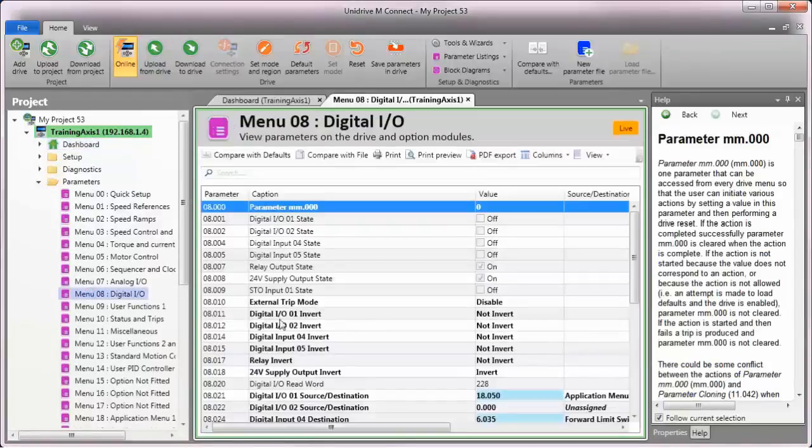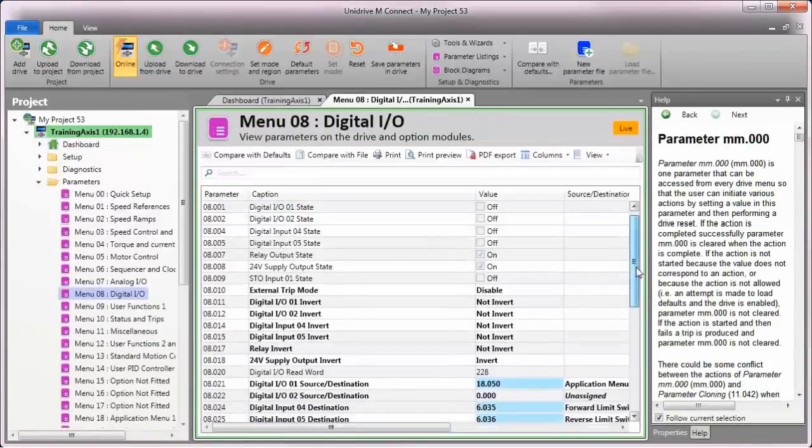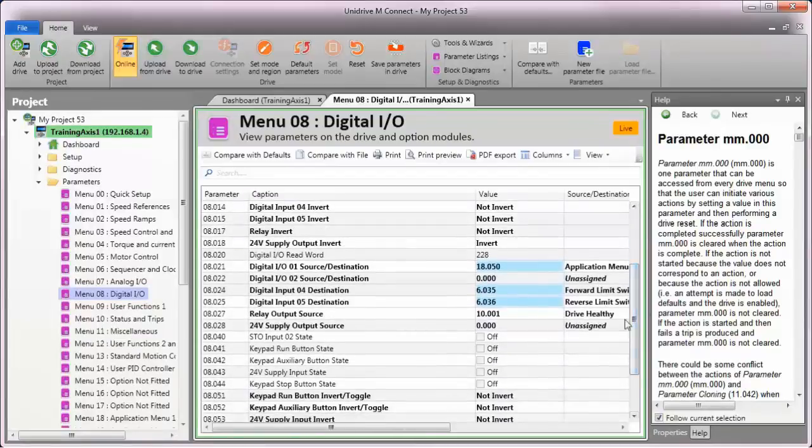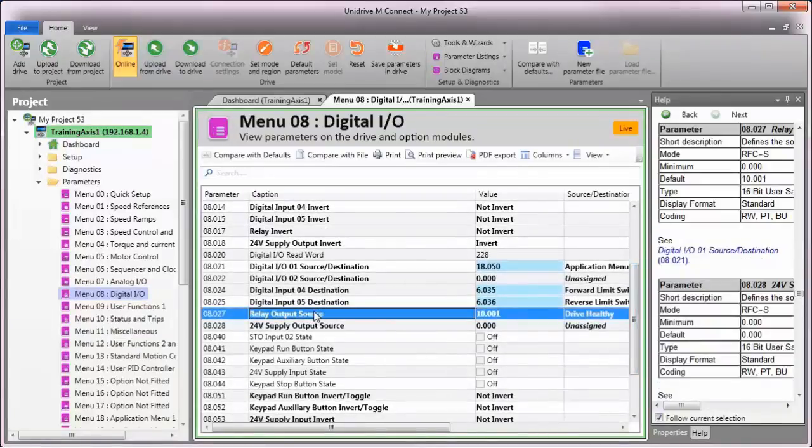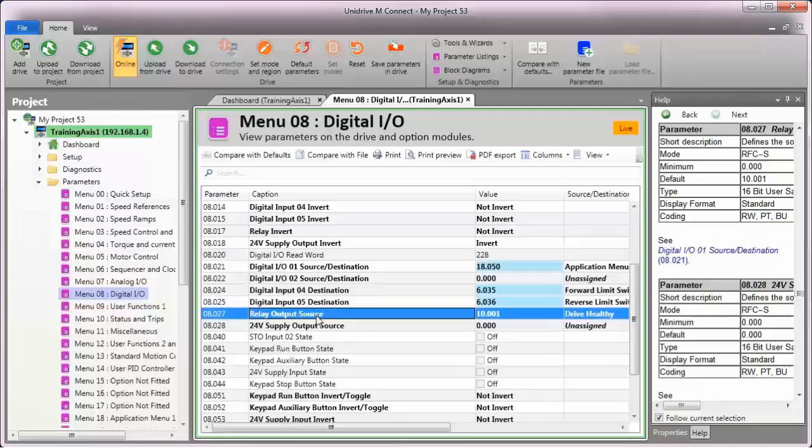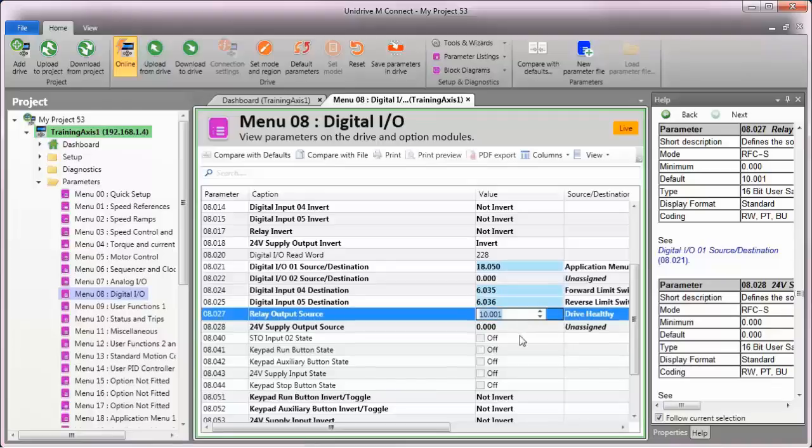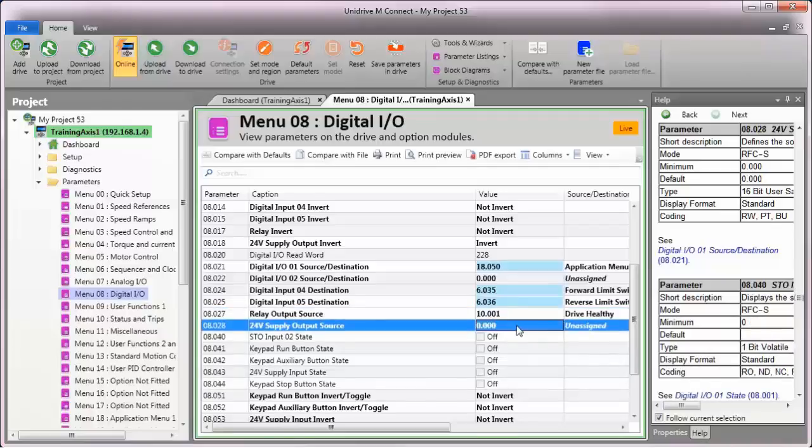The function of the relay contact is configured using menu 8 parameter number 27. By default, the relay is configured to activate as long as the drive is not in a tripped condition. This is accomplished by assigning the source parameter for the relay to menu 10 parameter number 1, which is drive healthy.